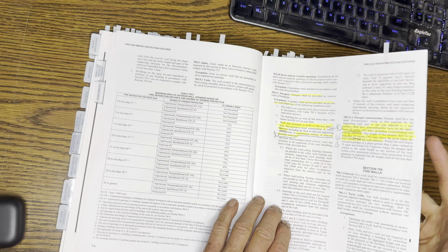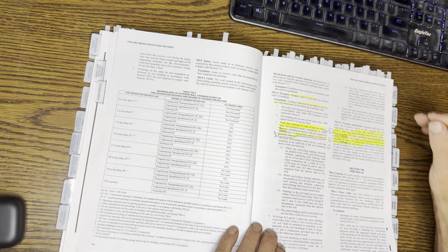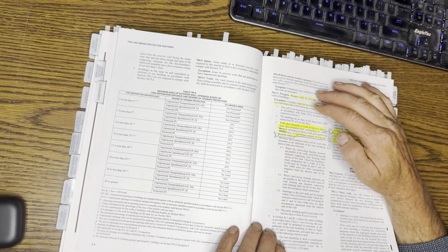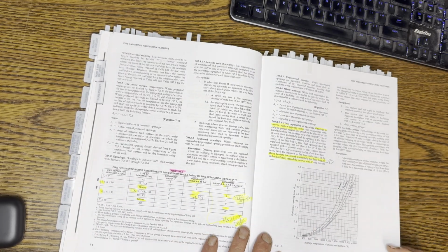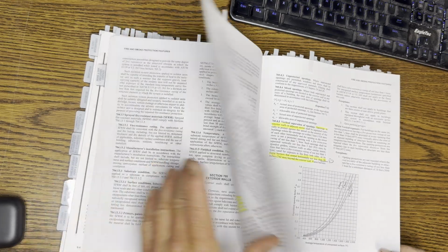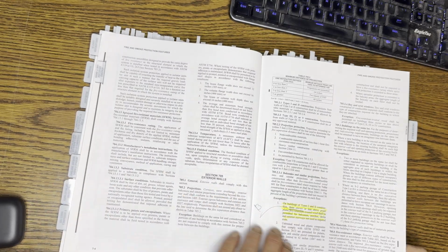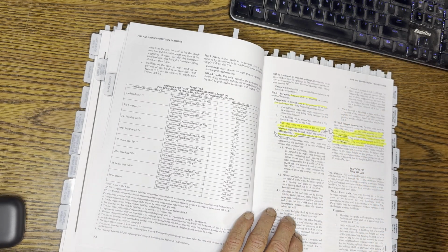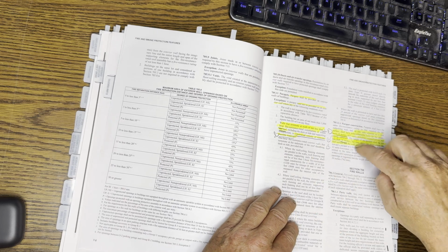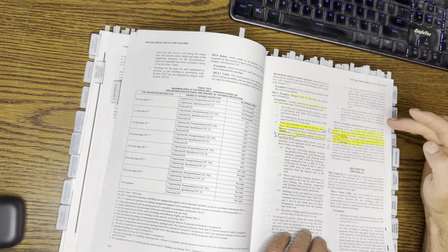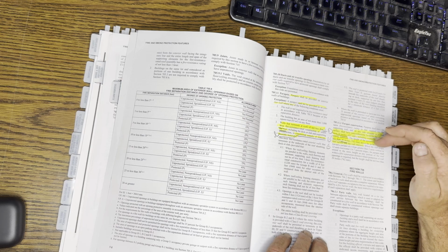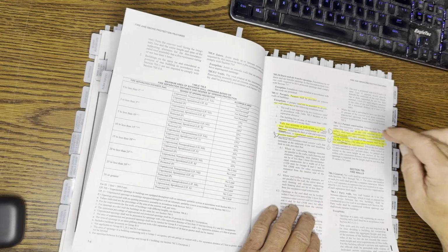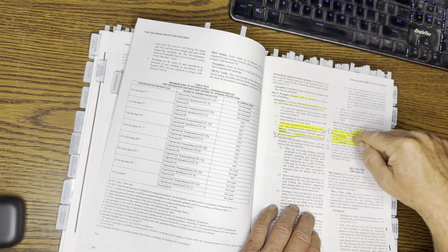So parapet walls, for firewalls, are going to be a little bit different, and you have a parapet wall definition that applies to firewalls. Let's see, what was 705.8? Bear with me. 705, exterior walls, yeah. You look at a building and they have these funky walls on the roof. Those are parapet walls. You will be asked a bunch of stuff from here: 18 inches flashing, non-combustible, 30 inches total height as a minimum. So just know, when it says parapet, go to 705.11.